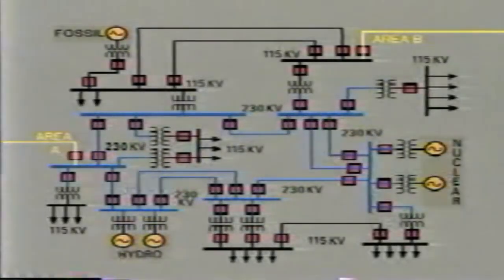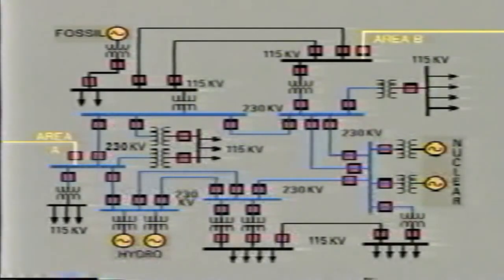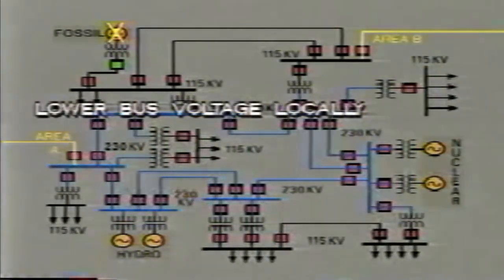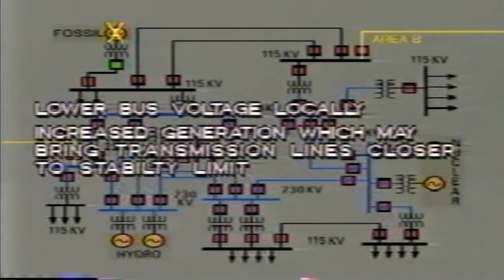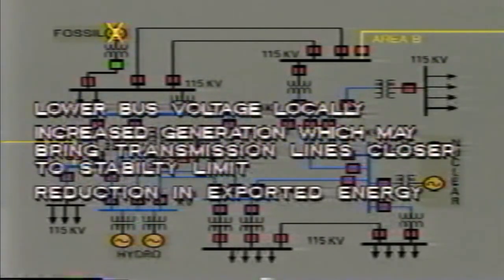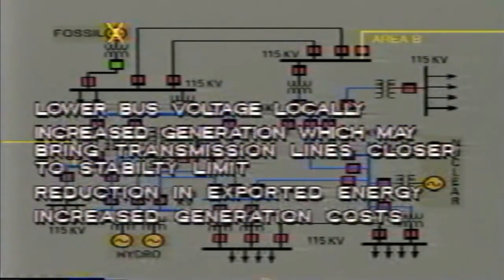Unfortunately, these ideal conditions are often disturbed by equipment outages, both planned and unplanned. For example, a generator outage for maintenance could result in lower bus voltage locally due to loss of reactive power. Increased generation in some other part of the system, which may bring certain transmission lines closer to their stability limit. Possible reduction in exported energy to a neighboring utility. Increased generation costs, as more expensive generation units will need to be placed in service.